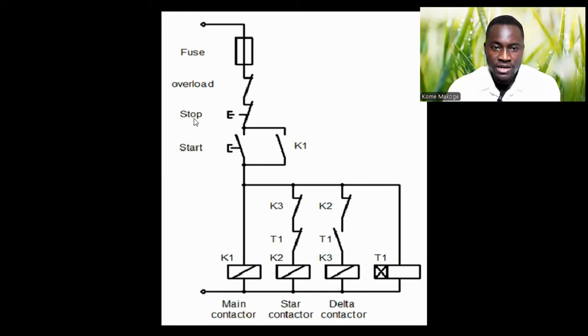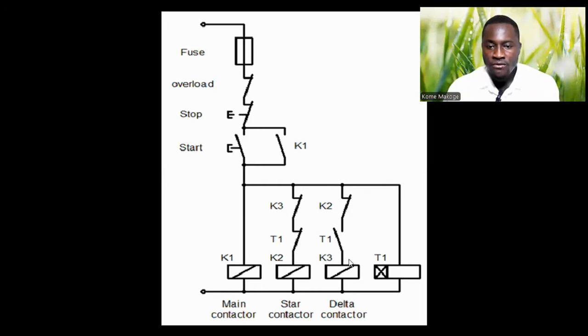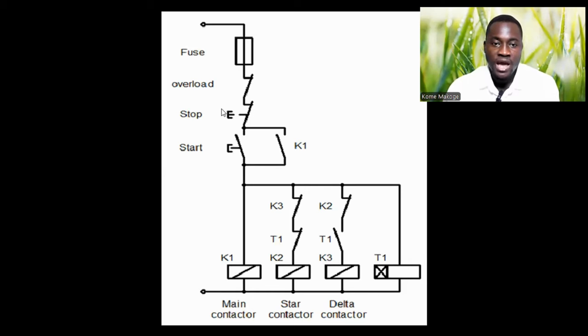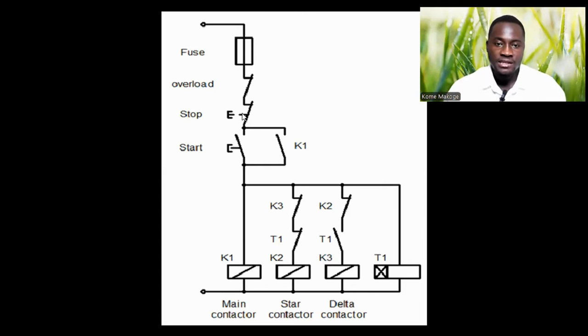When you press the stop push button, it prevents current from flowing down, so all the contactor coils are going to de-energize. K1, the main contactor, will de-energize. The delta contactor, which was energized, will also be de-energized. The timer coil will also de-energize because the stop push button has been pressed. This is how the Star Delta Starter functions. Understanding how the control system works allows us to carry out maintenance on site, do troubleshooting, and get our motor functioning correctly — which is very important.